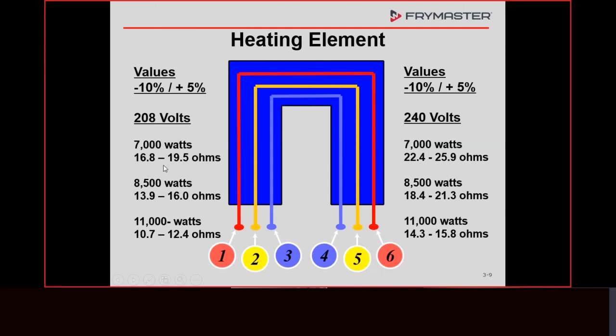before we install that element, and make sure they fall within this range. If you have the wrong size element, the voltage and the kW rating are stamped on the element, but it's good to go ahead and check it again. If you have one that's open, there's no sense in installing that element. It's bad. If the resistance falls in place, though, that means it's going to be the voltage and the kW rating that you need.